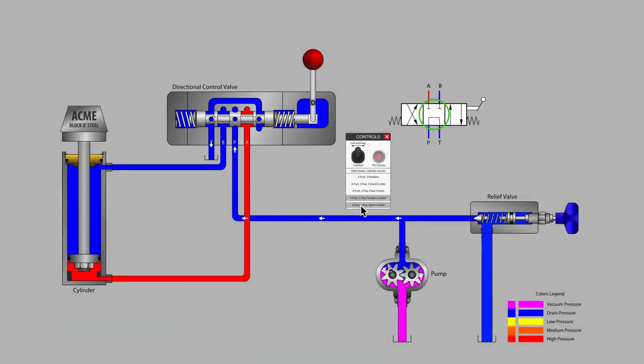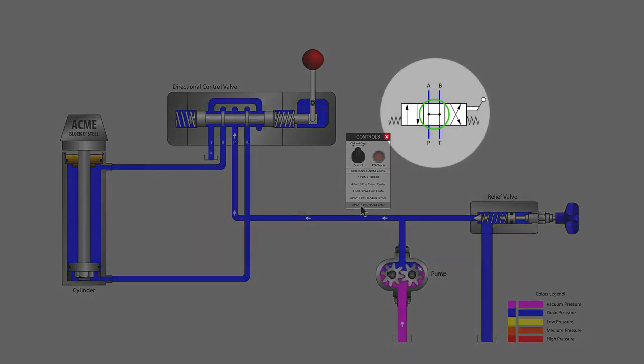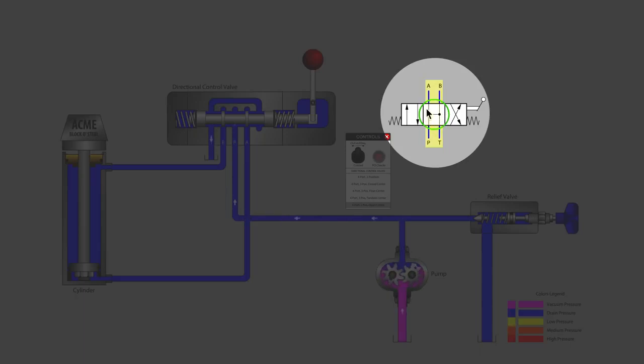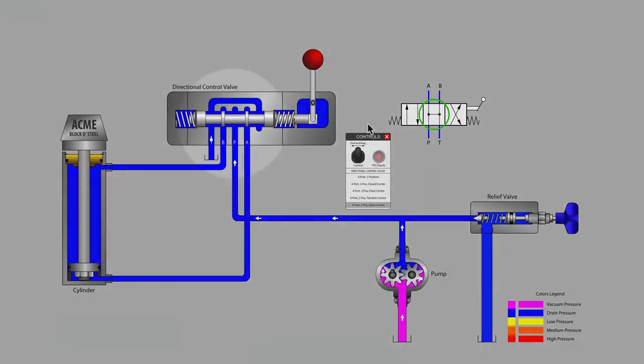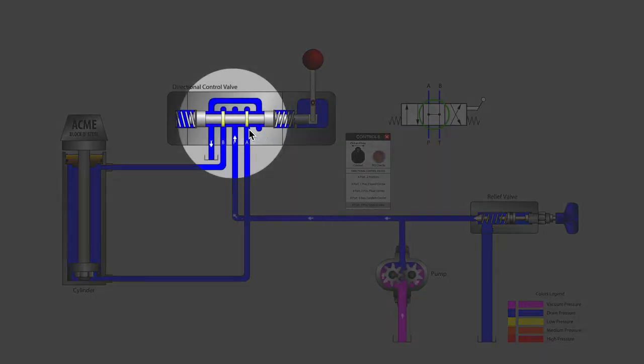Now let's switch to the open center valve. Notice in the symbol that all ports are shown connected together when the valve is in neutral. Moving to the cutaway, we see that the lands on the spool have been machined back so far that they do not cover any ports while in the center or neutral position.